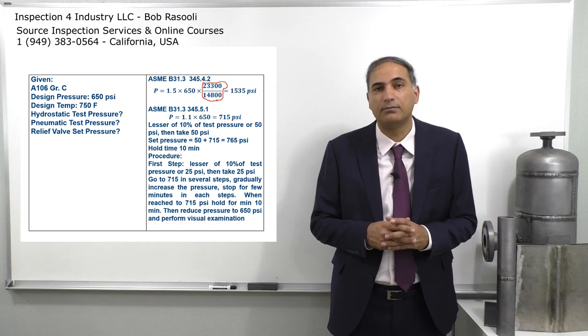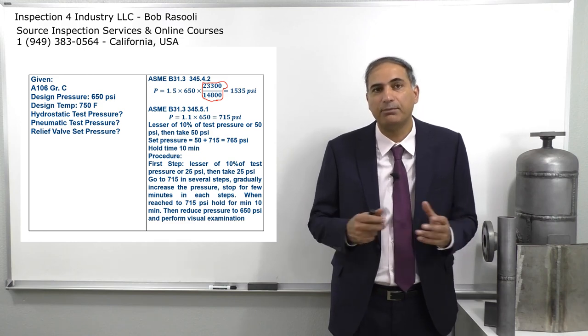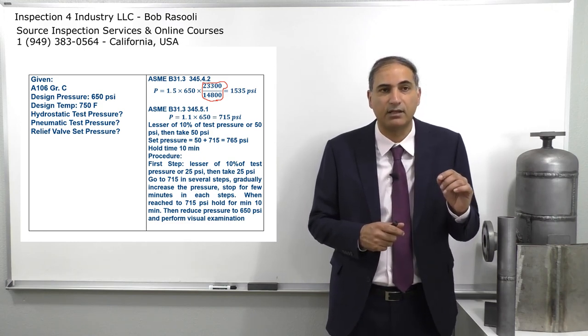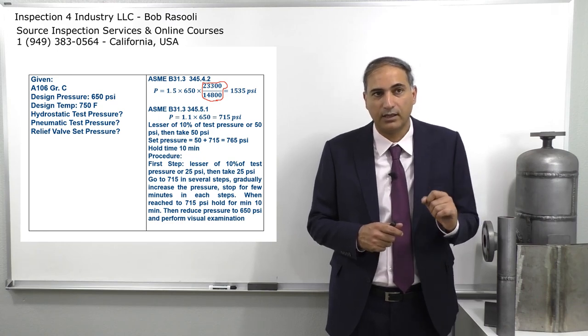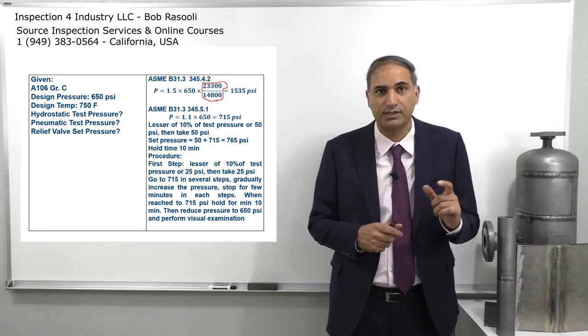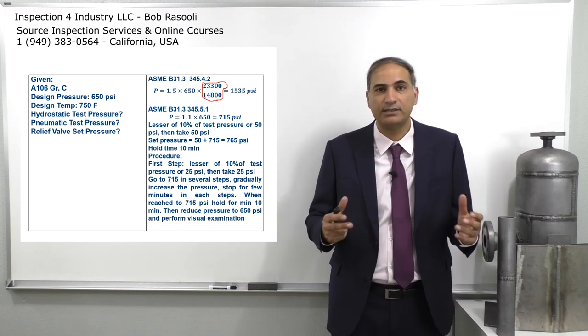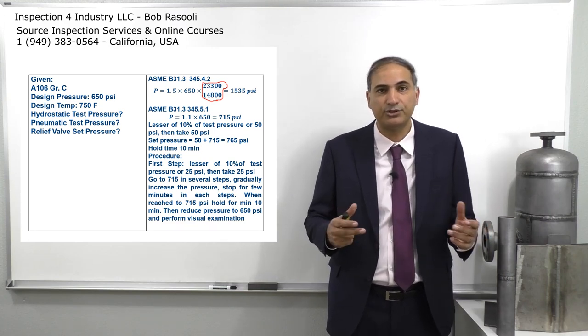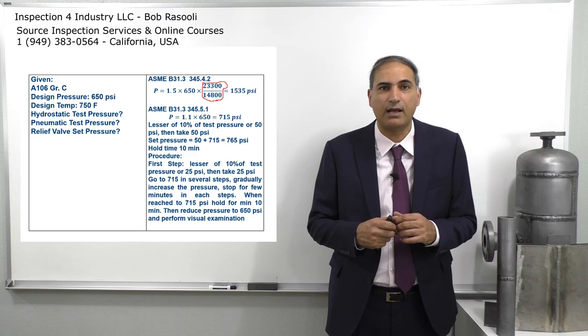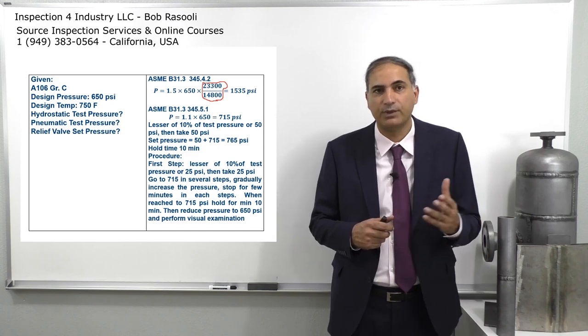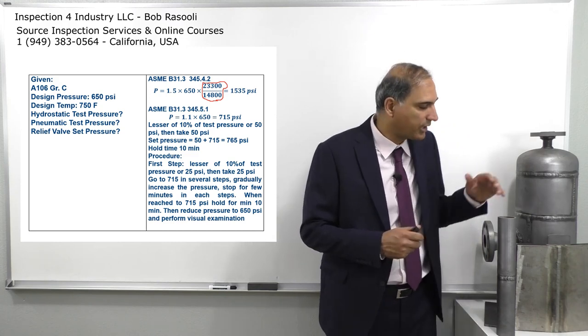I go to the A1 table to find the allowable stress at 750 degrees Fahrenheit for A106 Grade C, which is 14,800 psi. At room temperature, the allowable stress is 23,300 psi.